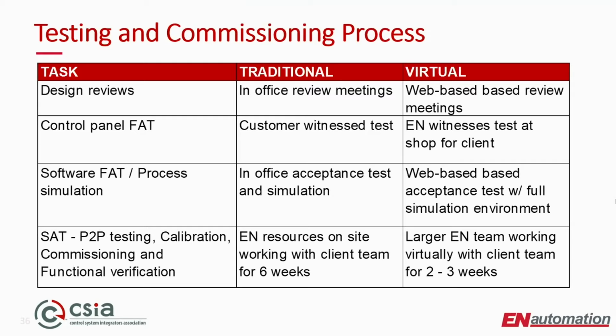But the biggest time commitment, and where we think we realized the most savings, is the on-site work. That involved the point-to-point testing, calibration, commissioning, and functional verification of the software. Typically we would send a couple of our engineers out to the site, and they would work with the client team, the operations and technical staff. But it would take about 6 weeks.